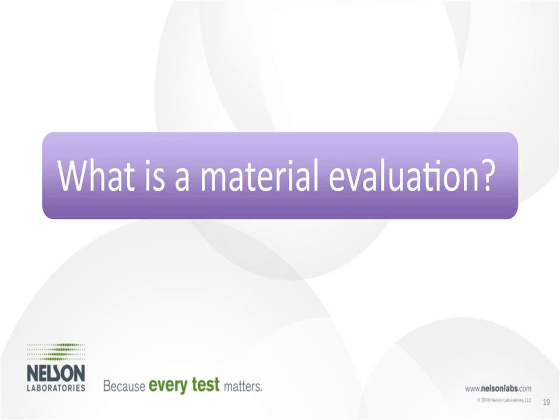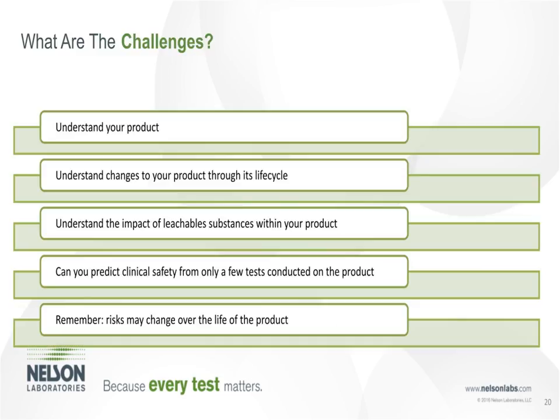Okay, so the main thing that goes into your BEP that a lot of companies are not doing right now is this material evaluation. Really evaluating what is in your device. And we've had companies that have sent in biocompatibility that went down to Home Depot to buy some stainless steel. We would not recommend that. Nothing against Home Depot. They're a great company, but not so great as providing medical device material. So this helps us evaluate what really goes into a medical device and the risk associated to it.